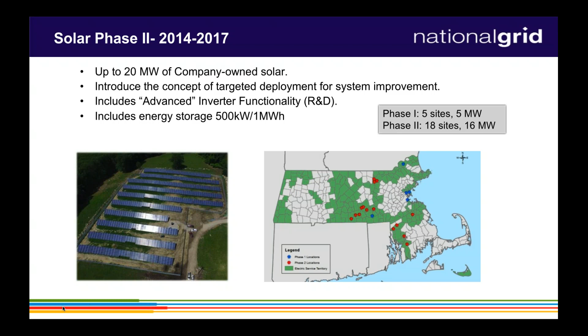So there's a lot of... Oh, volt var, it's a great function. It is, but knowing the settings and knowing where that site is really has an impact on the ramp rate you may put that at and some of the functions. So we do see advanced inverters being very beneficial. And this program, all the systems are up and running, and we've figured out what we think are the best settings. We're in the process of putting those out to the systems and actually seeing the results.